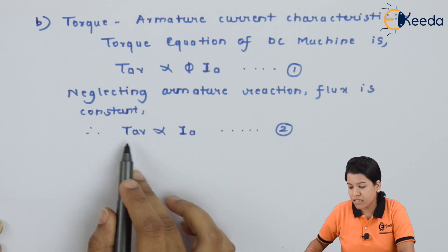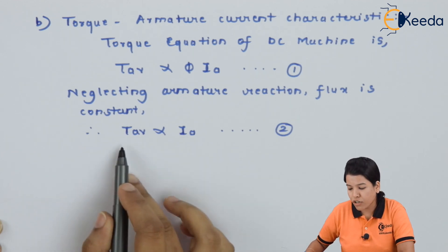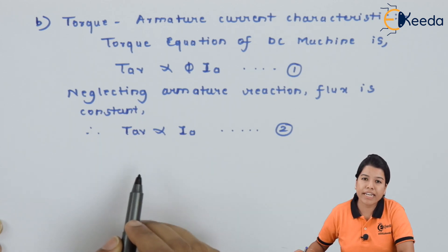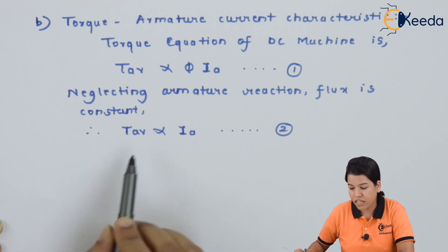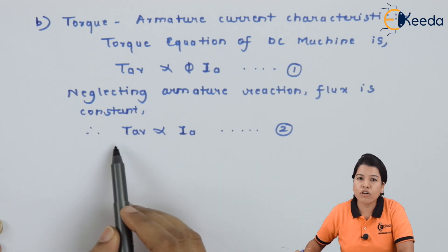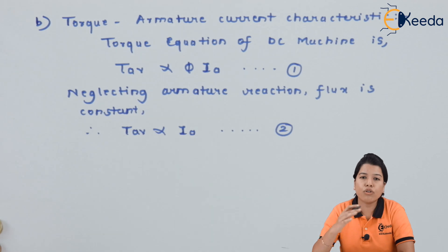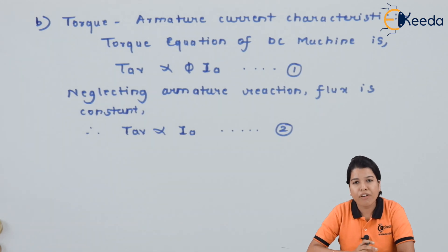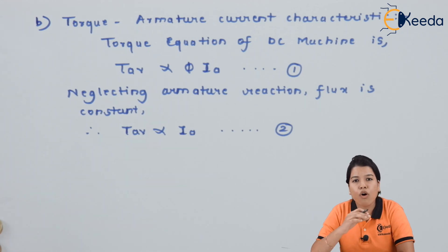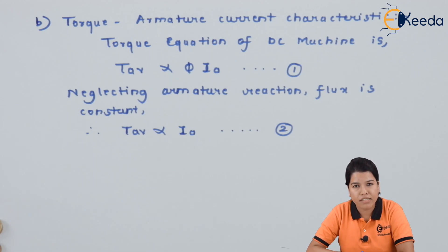As the armature current goes on increasing, the torque will also go on increasing. This happens only when we neglect the effect of armature reaction. At no-load condition, as armature current increases, torque also increases. But as the load goes on increasing, the effect of armature reaction cannot be neglected. Hence, there is a certain amount of flux change which impacts the torque value, and the torque will go on slightly decreasing.